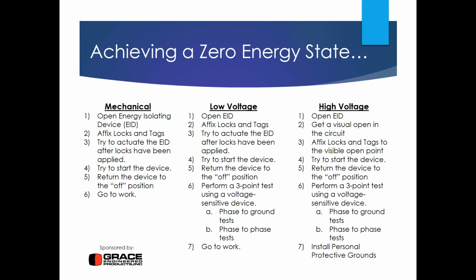Then, of course, we'll do the try test. We're going to try and start the device. Hopefully, the device will not start. If the device does not start, you return it to the off position, and at that point, according to 147, you're able to go to work.